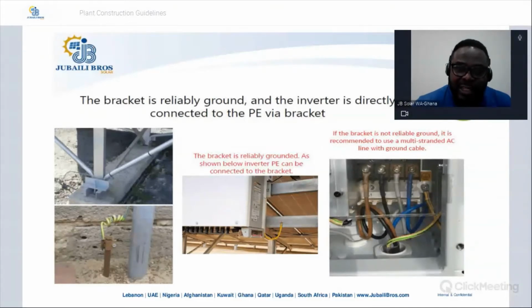Don't assume that when you ground the system to the metal bar, and because the metal bar touches the ground, that counts as grounding. No - please ground the metal bar to a very good earthing system, and make sure you have also grounded this inverter enclosure. Absolutely important.